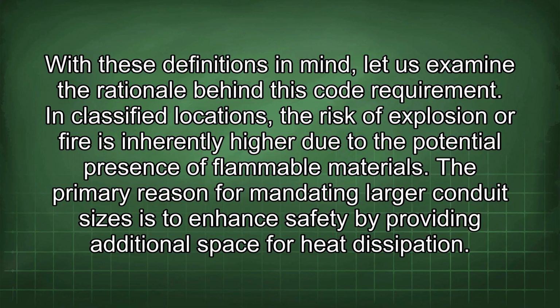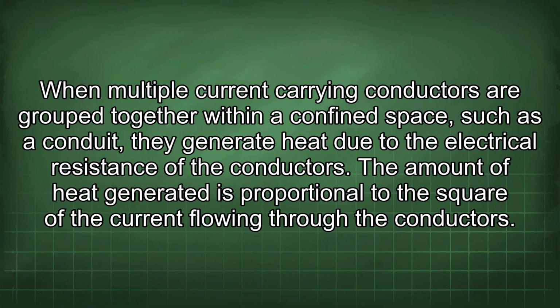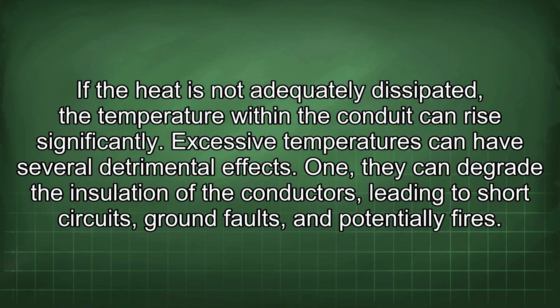With these definitions in mind, let us examine the rationale behind this code requirement. In classified locations, the risk of explosion or fire is inherently higher due to the potential presence of flammable materials. The primary reason for mandating larger conduit sizes is to enhance safety by providing additional space for heat dissipation. When multiple current-carrying conductors are grouped together within a confined space, such as a conduit, they generate heat due to the electrical resistance of the conductors. The amount of heat generated is proportional to the square of the current flowing through the conductors. If the heat is not adequately dissipated, the temperature within the conduit can rise significantly.